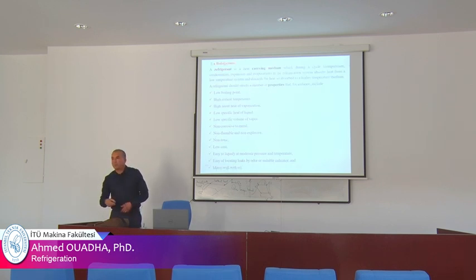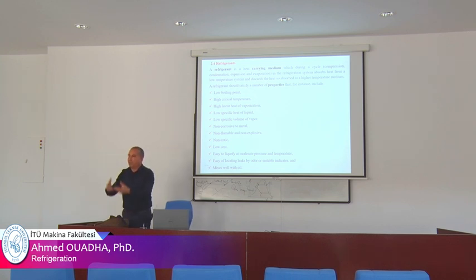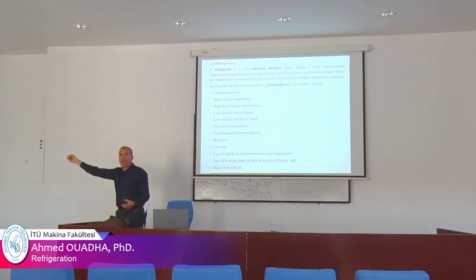So we go now to the last point in this chapter, on refrigerants, the medium used to carry heat from the evaporator to the condenser, because the refrigeration system carries heat from the cooling medium and delivers heat to the condenser to reject it to the surroundings. This is the principle of operation of a refrigeration system. A refrigerant, a cooling or heat carrying medium, is used in a closed cycle. The refrigerant should have selected properties or criteria to be used in an application.